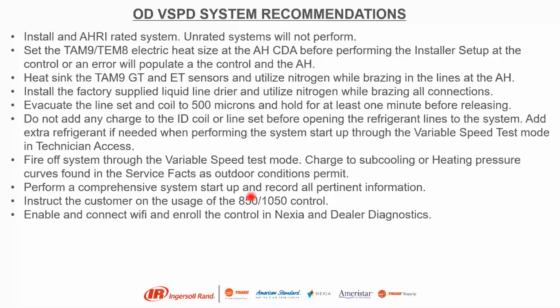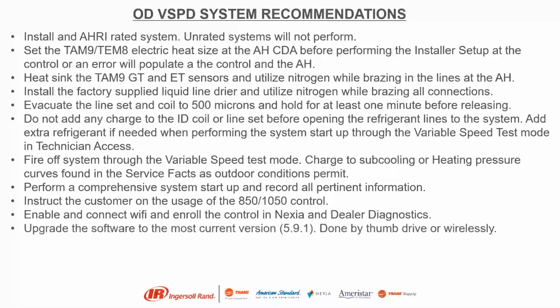Enable and connect the Wi-Fi and enroll the control in Nexia and Dealer Diagnostics. This is huge because if we do have any issues, you can share that AUID number with us here at tech support, or somebody in the office can actually log into it and decipher the information from the past 30 days of runtime. So it's really a valuable diagnostic tool. And we can also see if possibly the homeowner's not changing their filter through static pressure.